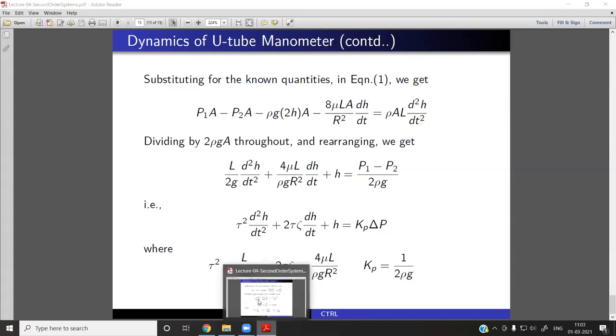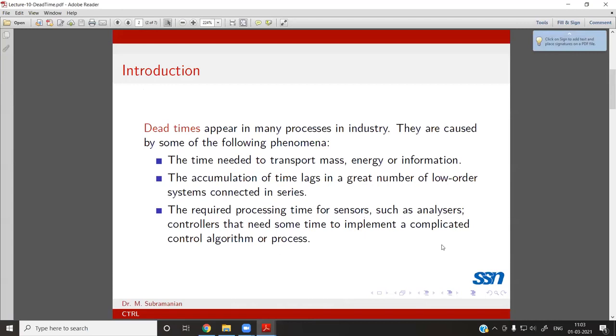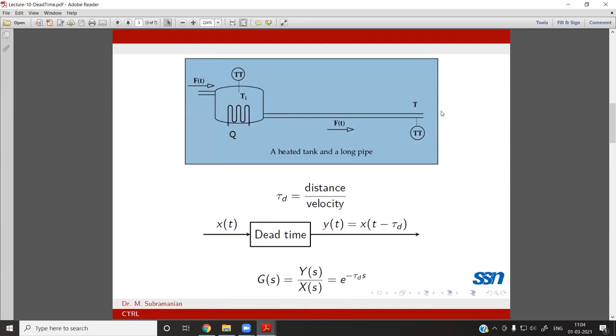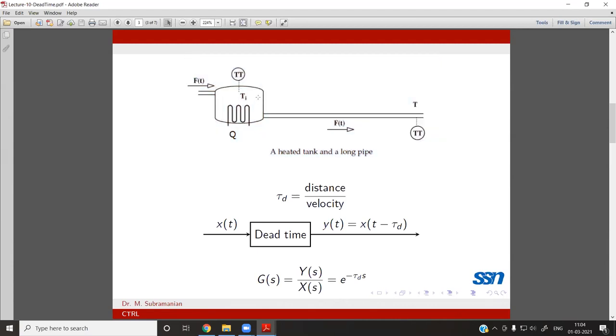As the last aspect, we discussed dead time, which we will start from now. Dead time arises whenever you have a measurement lag. For example, instead of taking the measurement at the tank or tank outlet, if you delay the measurement over some distance, you will see a delay in the measurement by the amount τD, which equals distance divided by velocity. The response at the outlet will lag by amount τD.